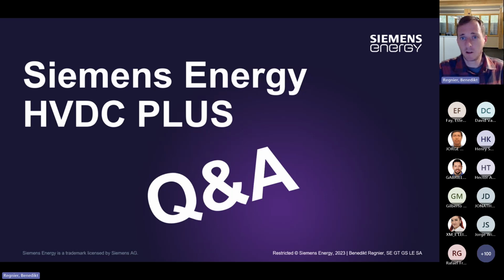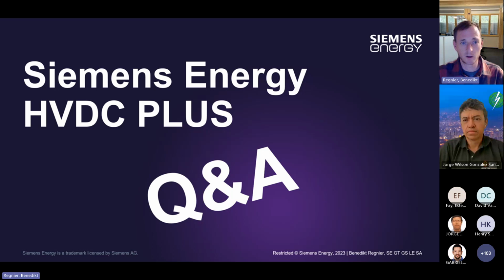Whereas for VSC, you can do it with, at least on one side, basically no grid, like we do for offshore. We are generating the grid from scratch. But then the second station needs to be somehow in a stable grid, because the energy needs to come from somewhere. We can do a lot. And now also with the grid forming controls, we have a lot of possibilities to work also on two sides with weak grids. So if you have a weak grid, then the VSC solution is definitely a much better choice than LCC, and you can operate really on a wide range here.